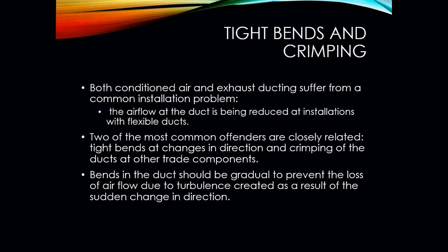Okay, both conditioned air and air exhaust duct, can suffer from common installation problems such as tight bends and crimping. The airflow at the duct is being reduced at installations with flexible ducts. So you have two of the most common offenders that are closely related to air velocity and airflow issues, simply due to the fact that the ductwork is not installed properly. We are having tight bends or crimping going on where that ductwork is being connected to the actual area where the air is supposed to come into the space.